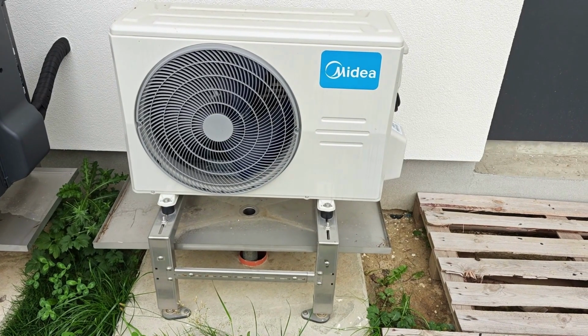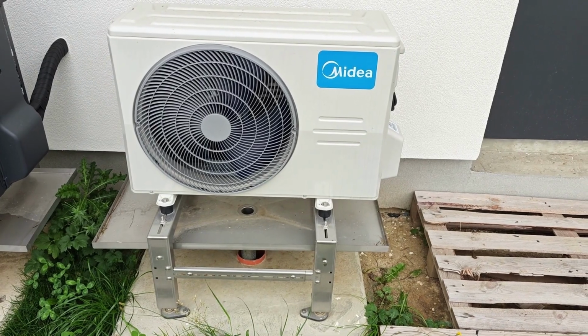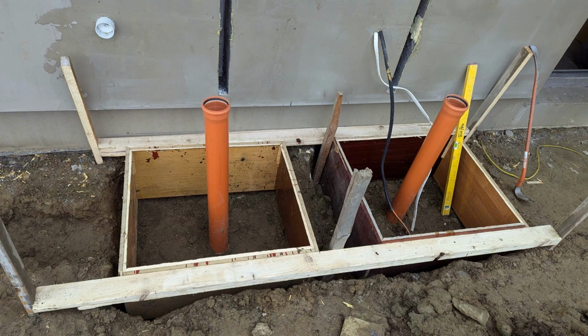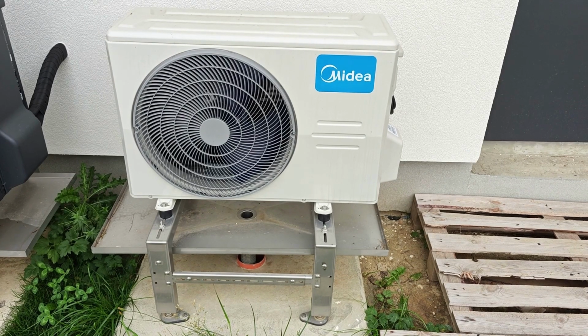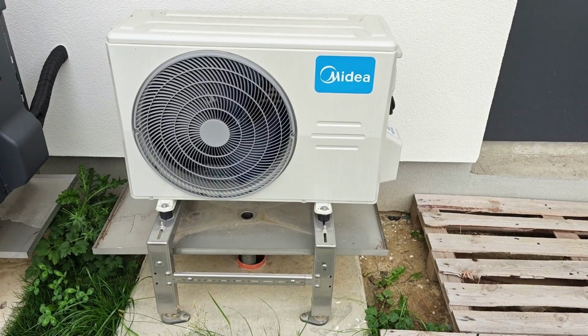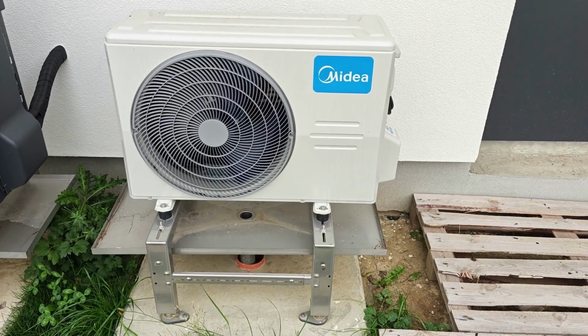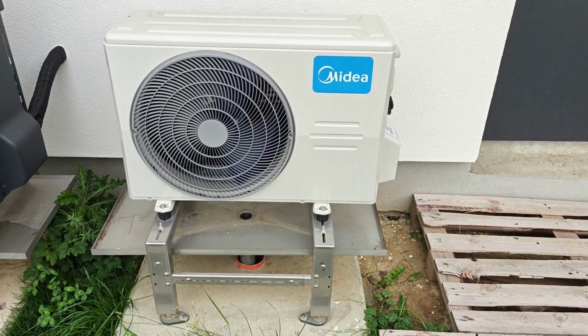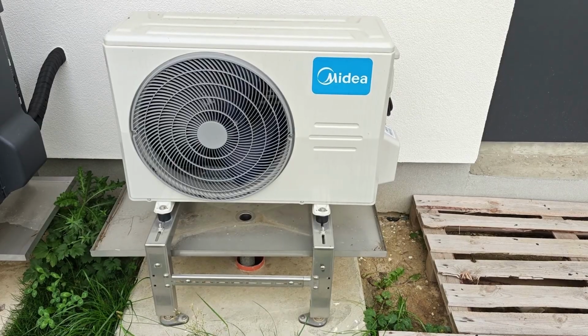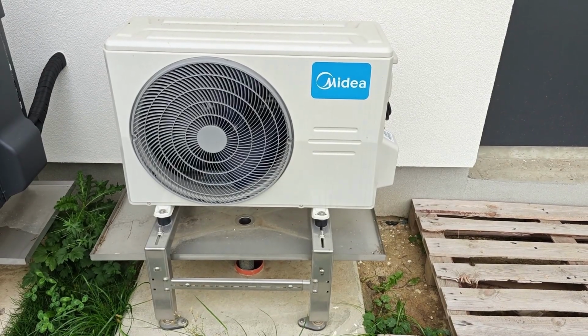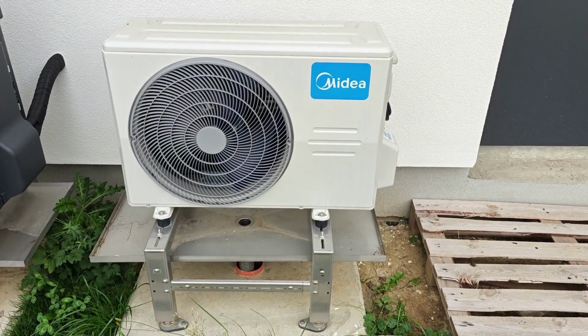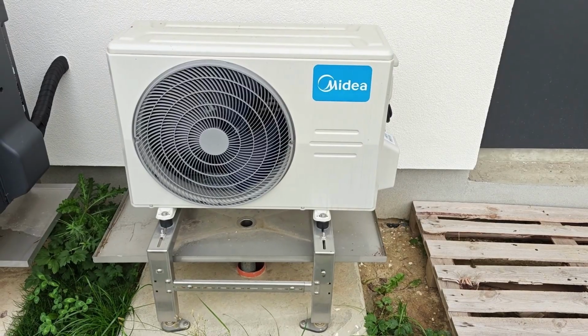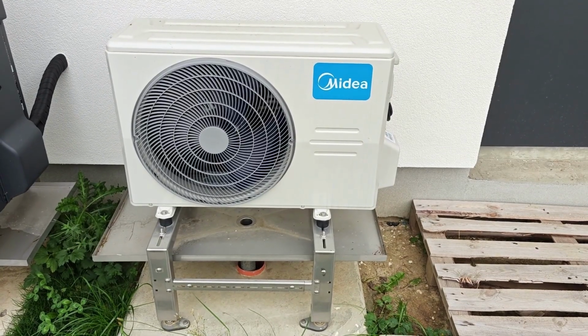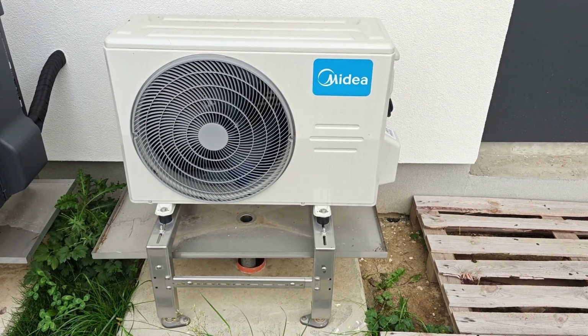The unit is located on a stainless steel stand with a drip tray. Its power is approximately 5 kilowatts, serving both to cool the building during the summer and to provide heating in the winter. Last winter season, the unit was utilized for supplementary heating of the building during periods of low temperatures. At that time, there was no drip tray installed, and there was no problem with condensate freezing during the frost because water freely flowed onto the concrete. However, now after installing the tray, I will have to monitor the situation because condensate might freeze on the tray, and it will probably end up with the use of a heating cable.